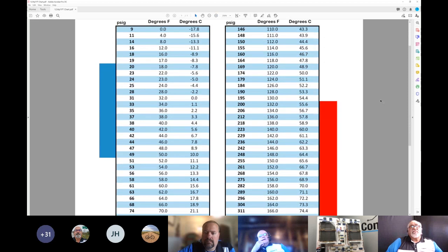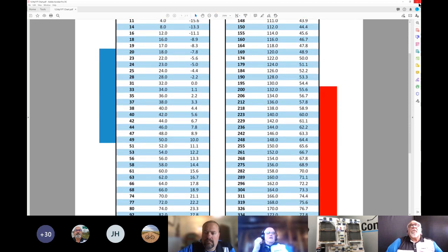Several of you have indicated you'd like the link to the Dropbox. If any of you want all of these documents, including the mega PowerPoint, just let me know and we'll send it to you. Just make sure that whatever system you have, you must use the relevant PT chart for it. The one we use today would not work on a 134A system. The concepts are the same, but you need the chart to match the refrigerant.